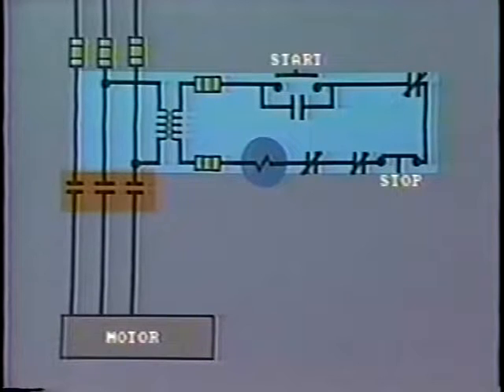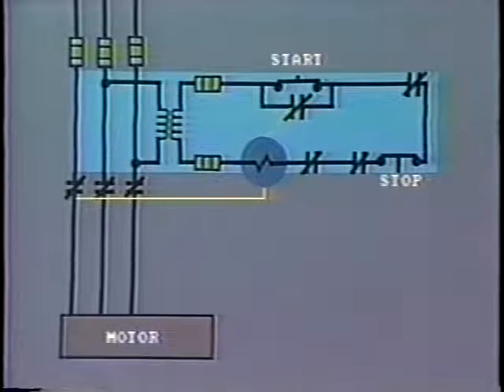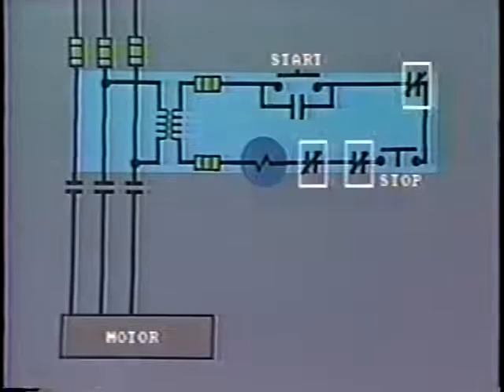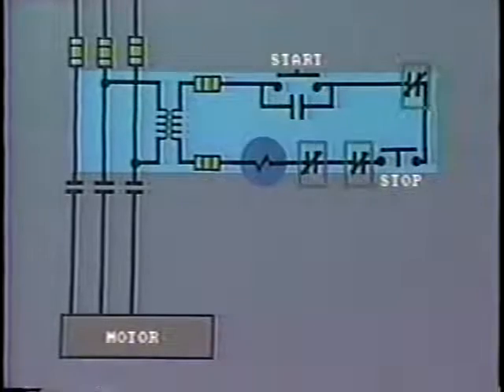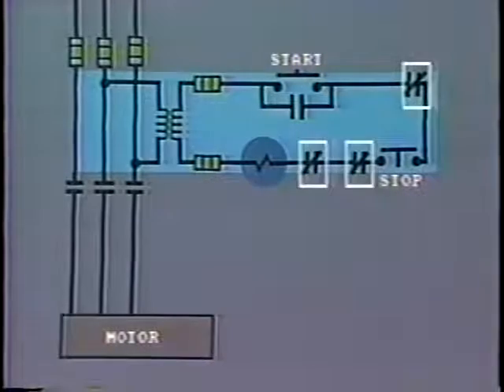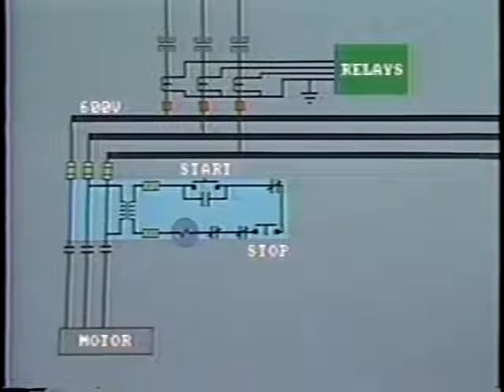In order to close the contactor contacts and start the motor, this contactor coil must be energized by simply closing the push button. This will close the seal-in circuit, and the push button can now be released. As long as there is voltage on the contactor coil, the contactor remains closed and the motor will run. To stop the motor, we must press the stop button to open the circuit. Protective relays operate in the same manner, that is, by opening their contacts in the contactor coil circuit. So let's now add the protection devices.